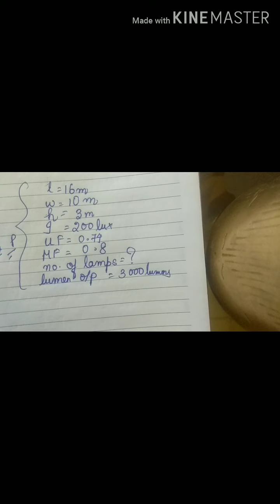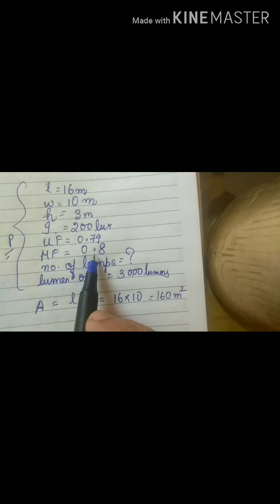First, you have to find out the working area. So the working area will be length into width, that is 16 into 10, 160 meters squared. The required illumination level is already given as 200 lux, and the lumen output of each lamp is 3000 lumens. Along with the utilization and maintenance factor. So the number of lamps will be E into the area divided by the lumen output of each lamp multiplied with the utilization factor and maintenance factor.